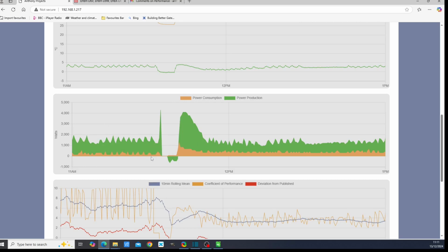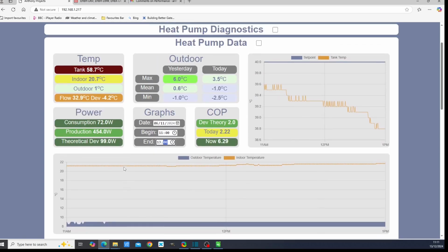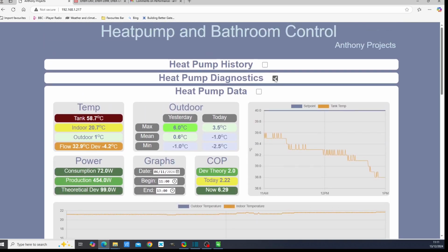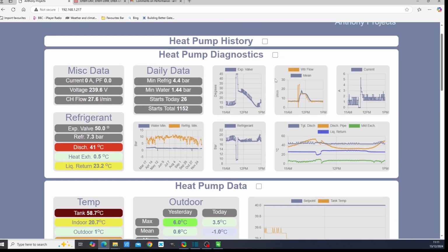you can see that there are no particular differences between the left side and the right side in terms of environmental conditions. Let's go up to heat pump diagnostics. You can see here the expansion valve always starts at 45 degrees and then ramps back in. But you can see that from about 1 p.m. onwards, it's got back to the minimum position. And you can see here, the expansion valve is pretty much at the low point anyway.